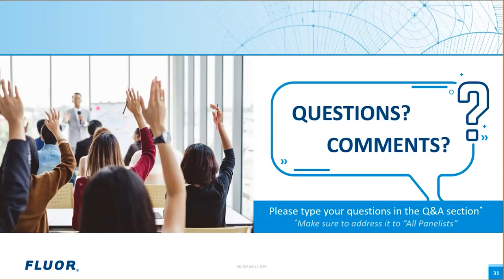Yeah, thanks. Well, I think IEC doesn't actually go into detail on any kind of ratio. It says the safe response time, or the response time of the safe, should be less than process safety time. And as you said, it is mostly the client spec that defines, and in most cases, clients tend to offer 100% margin as a starting point. Where you are in a tricky situation where it is not possible to reduce process safety time, or increase process safety time, to revisit the safe response time, the margin could be reduced on a case-by-case basis, considering other factors such as accuracy and uncertainty in the actual final designs.